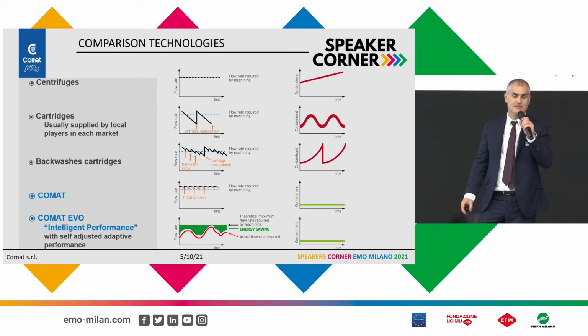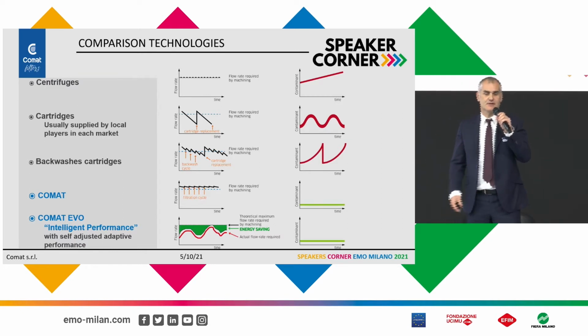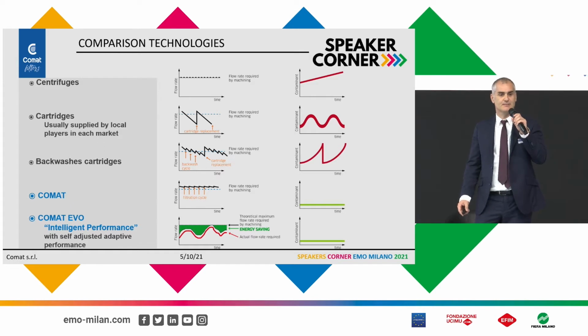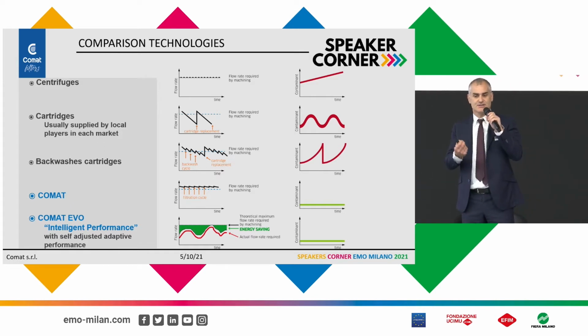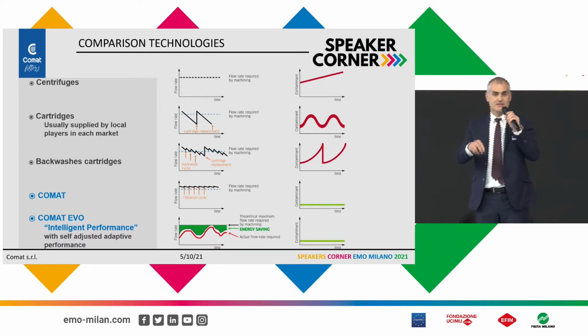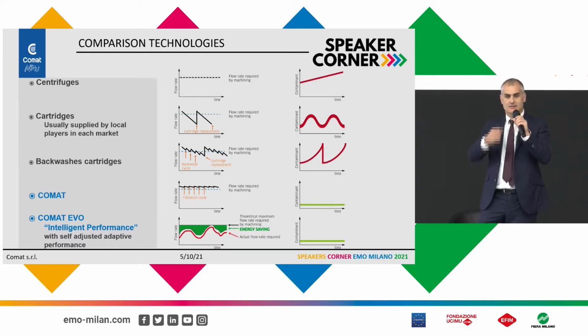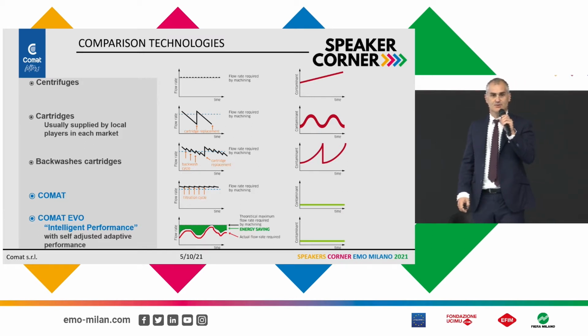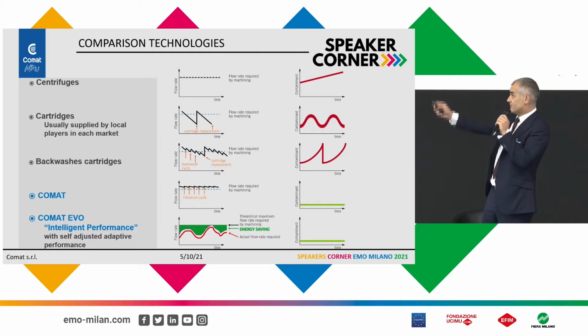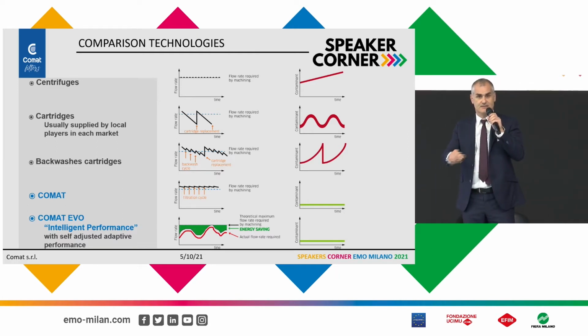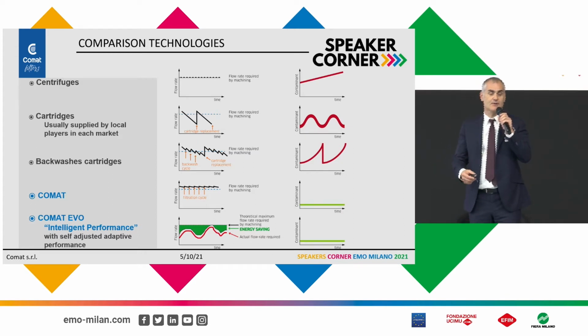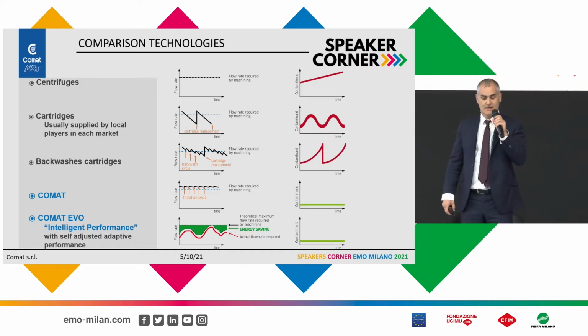The main competitor to our system is actually backwash cartridges. Backwash cartridges are cartridges that get backwashed, effectively revamped, at predetermined intervals, and the cartridge is backwashed using compressed air so that it can improve its performance. But as you can see, think of blowing into a flute. When you backwash the cartridge, as you blow into the flute, the air starts to get out of the cartridge fairly soon, and so the effectiveness of the backwash diminishes over time. As a result, the performance of the backwash cartridge also deteriorates to a point where the flow rate is below the one required by the machine, and at which point you have to replace the cartridge.